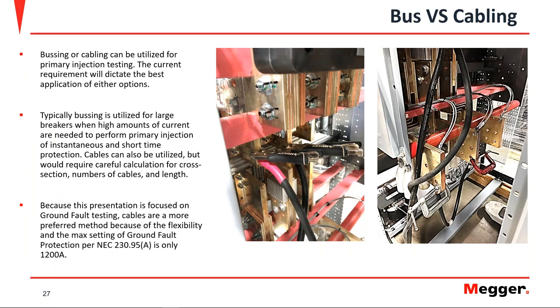For connections, you have the option of cabling or bus. Since the maximum current needed for ground fault testing is 1,200 amps regardless of breaker size, cabling is preferred — it is easier to connect and manage in the field. We can establish that cables will be enough to perform these particular measurements.